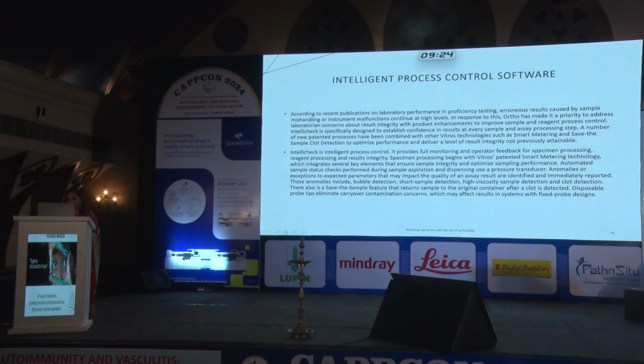According to recent publications on lab performance in proficiency testing, erroneous results caused by sample mishandling or instrument malfunctions continue at high levels. In response to this, Ortho has made it a priority to address laboratorian concerns about result integrity with product enhancement to improve sample and reagent process control. IntelliCheck is specifically designed to establish confidence in results at every sample and assay processing step. A number of new patented processes have been combined with other Vitros technologies, such as smart metering and save the sample clot detection, to optimize performance and deliver a level of result integrity which was not previously attainable.